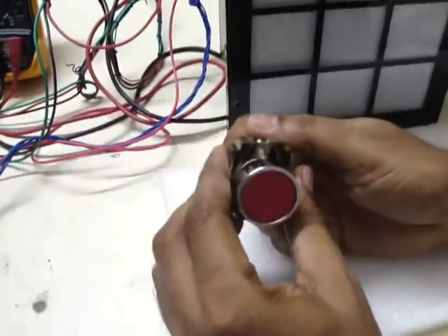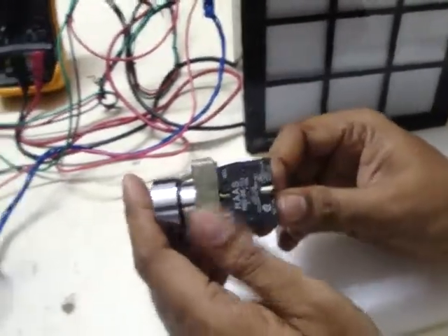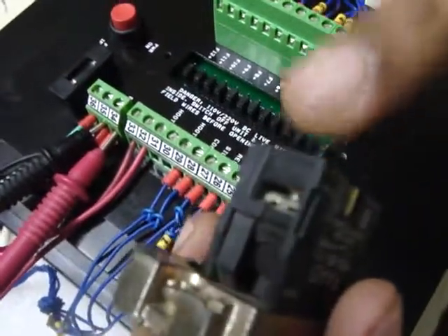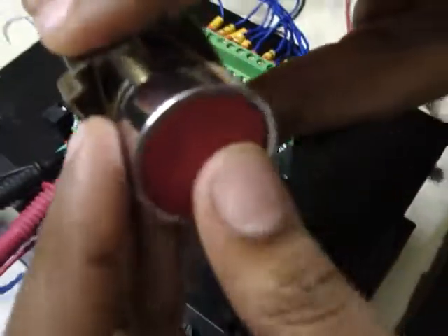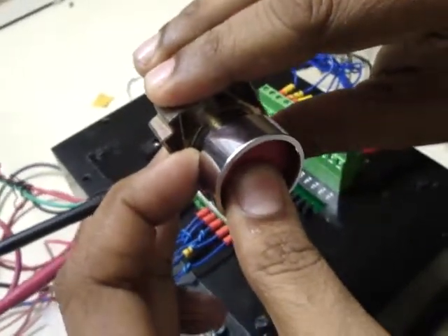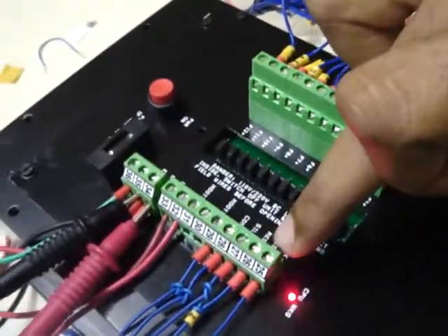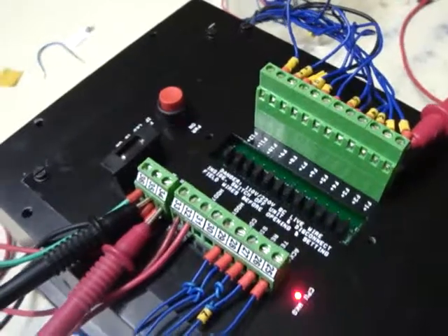The push button arrangement normally provided in the panel is like this. There will be a 22.5 mm push button with an NO element. The terminals from either acknowledge, test or reset will be connected at one side. The other side will be looped and connected to the common. So at the front side, when they press acknowledge, the contact will close, and the acknowledge input will take the input, and the window will become steady.